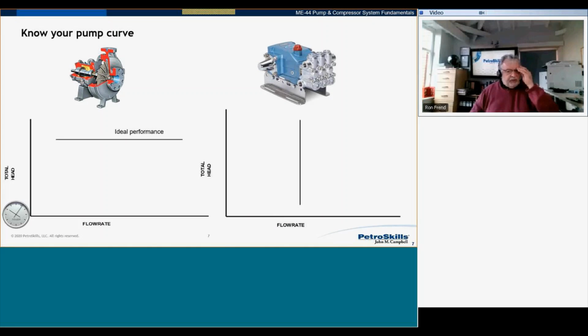Let's start simply, just a quick reminder, what is a pump curve? Because remember, we're going to develop a system curve. And a system curve depends on your particular system. The pump vendor cannot tell you what your system curve is. You have to do this, but the pump curve, the vendor will tell you. Ideally, if you've got a centrifugal pump, then the centrifugal pump has an ideal performance curve, which is a flat line. But because of friction losses, shock losses, and so on, you're not going to get a flat line.